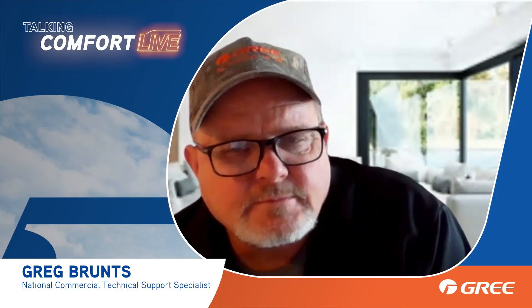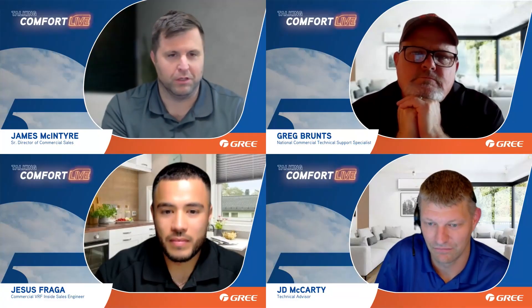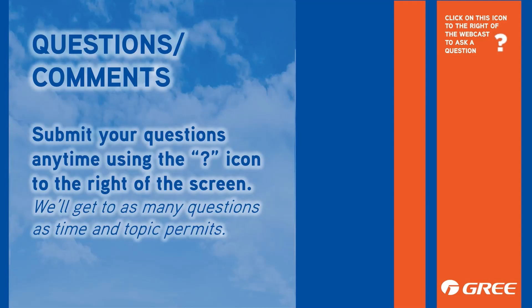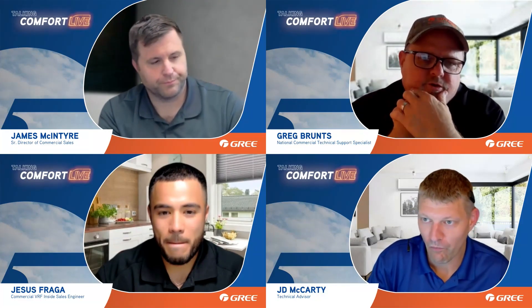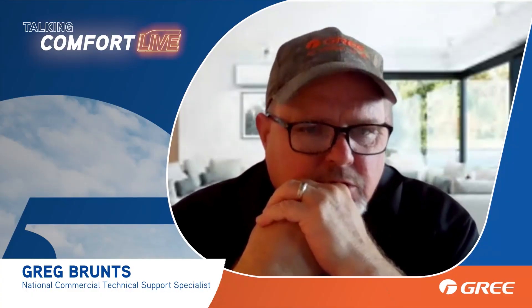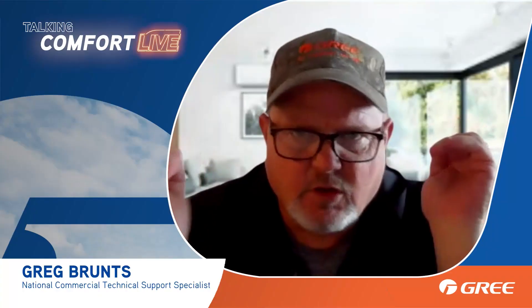To nerd out a little bit — one reason I don't care much for the damper system in that regard is that if I've got a five-ton unit, I'm just distributing less air. I'm taking a five-ton unit and dumping only 40 to 50 percent of that CFM or capacity somewhere, but I'm still running a five-ton unit. Sure, you might get better comfort if it's all set up right, but is it going to save money? Most of us hosting this webinar agree it won't.